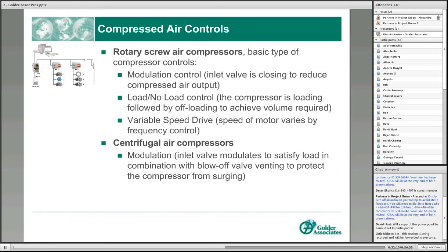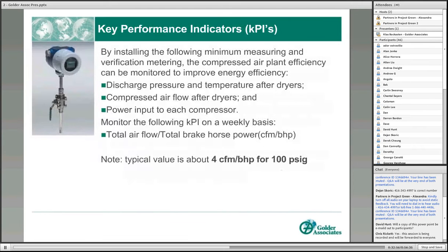For larger installations, the centrifugal air compressors typically have modulation with the inlet valve modulation, so you're closing a valve on the inlet side of the air to the compressor, choking it down to approximately 70% of the compressor full output. Below the 70% point, typically you would blow off compressed air, vent it to atmosphere, and this is simply to avoid surge and destroy the engine or the compressor. So again, centrifugal machines are great. They operate oil-free, and particularly at high loads. At part loads, they are a very inefficient piece of equipment.